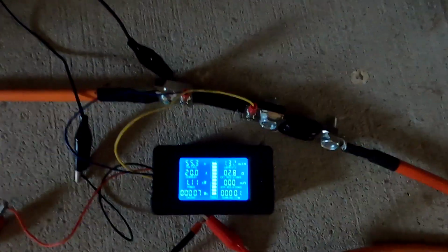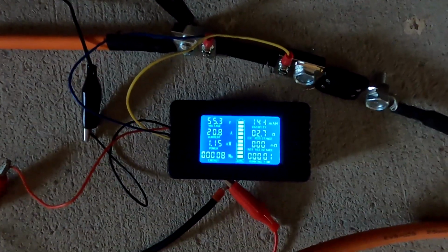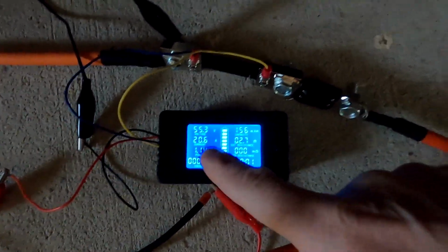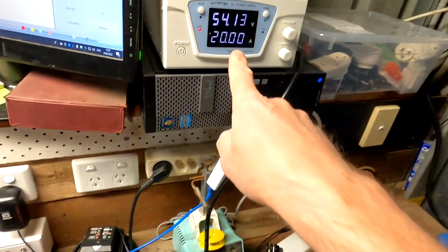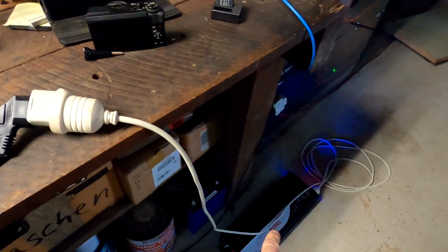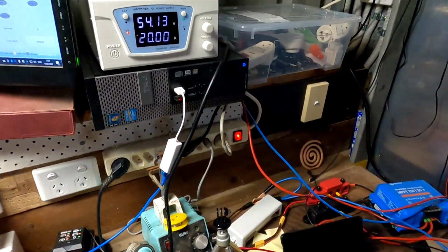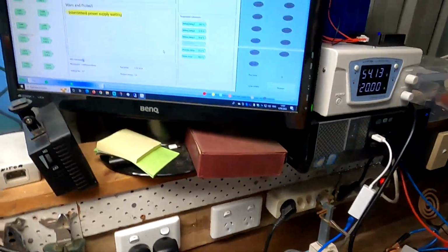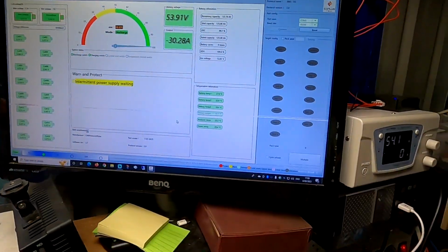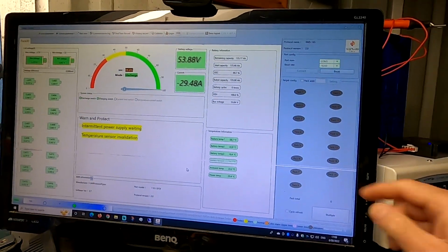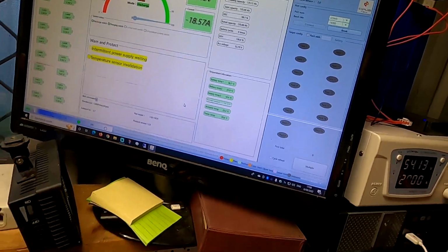Well, that cannot be true, right? 20 amps here is 20 amps on the other side. There would be 100% efficiency of the inverter and the power supply here. So it shows us 30 amps here, so we probably have to go with this one. But then our smart shunt is not right here. Why is this one not correct?